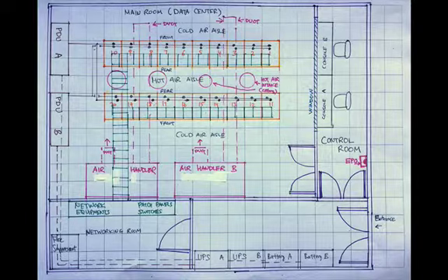Since the data center is rather small, the electric conduits run from the PDU directly to each server row via direct connect power. For redundancy, there are two sources of electric power, routed through two PDUs. Each PDU runs at 50% capacity, and each rack has two power strips, each connected to a separate PDU. Power cables are routed through flexible conduits, or whips. There are two air handlers for redundancy. Each is running at 50% capacity and can take over the entire load if one were to fail. The EPO switch is also located as soon as one enters the control room.